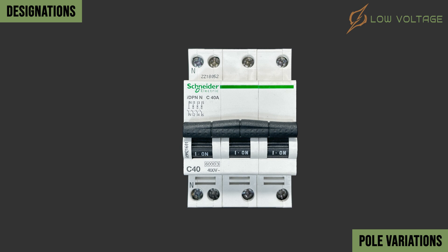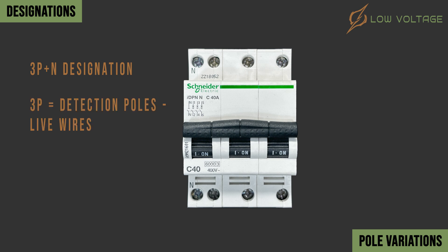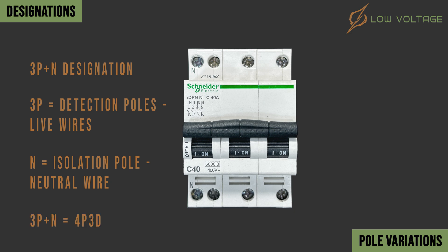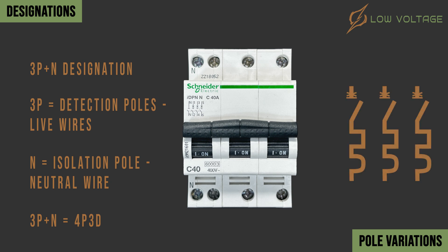This is a three poles plus neutral MCB, having a 3P+N designation, so it can be considered as a four poles MCB. Three are for detection used for live wires, and the last one is for isolation used for the neutral wire. So it can also be defined as four poles, three detection, or 4P3D, having three detection symbols and one isolation symbol.